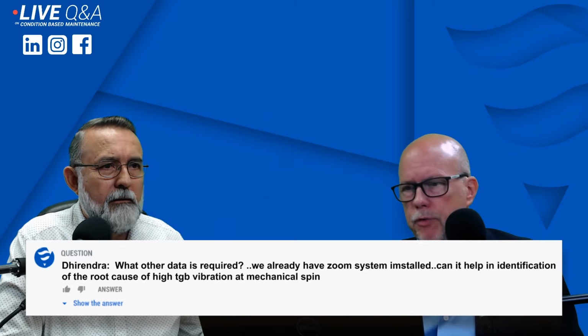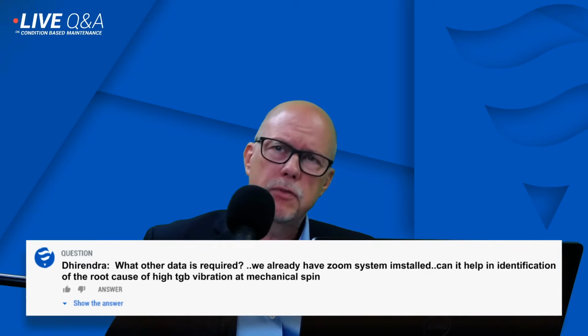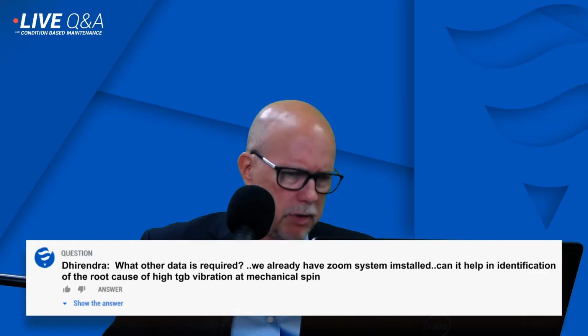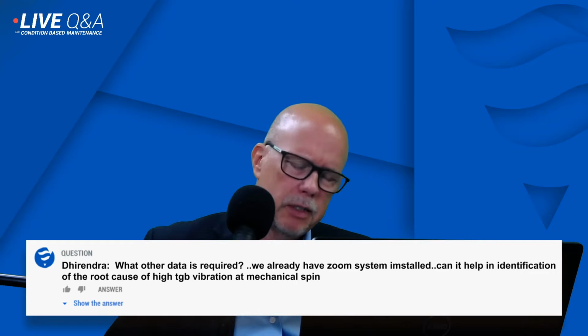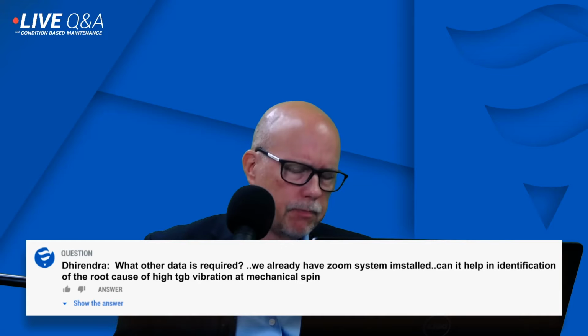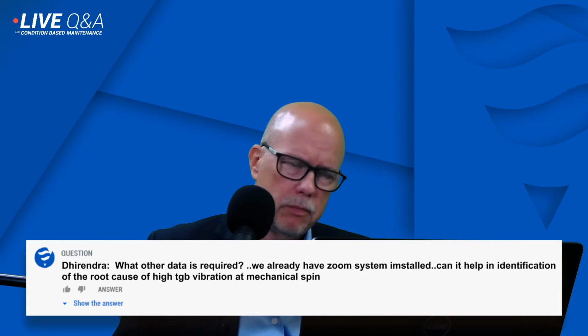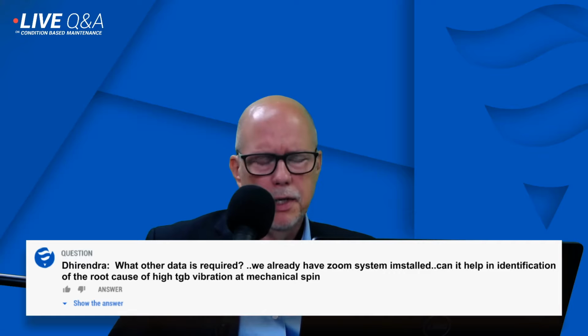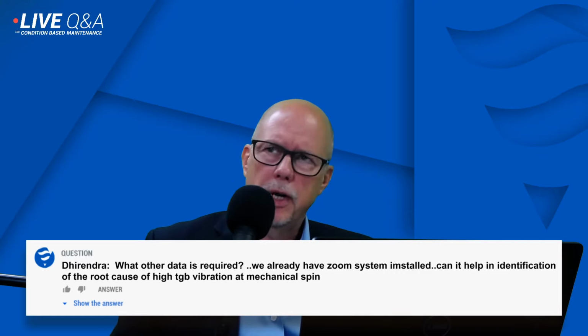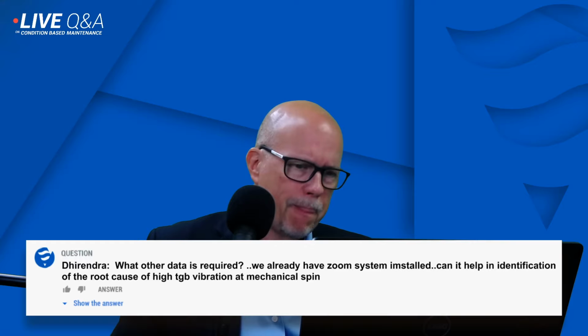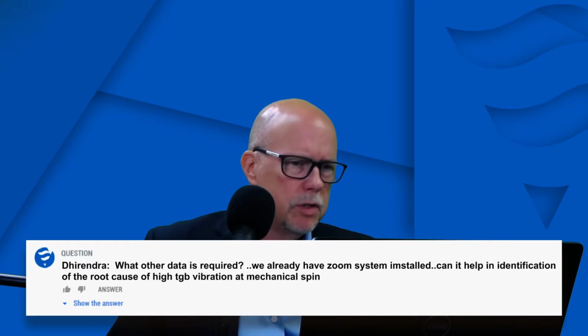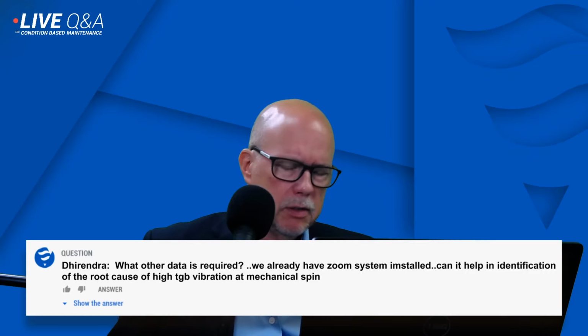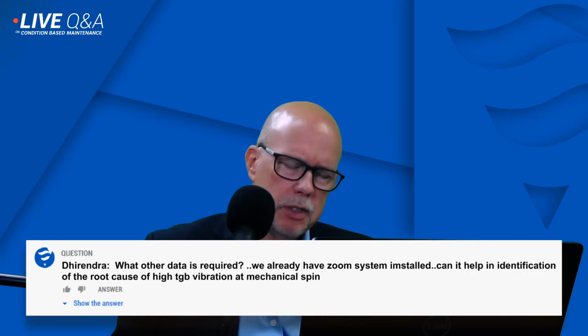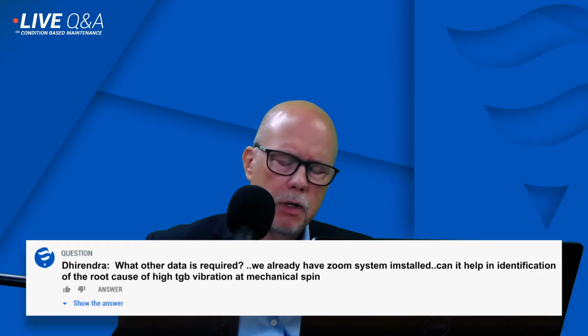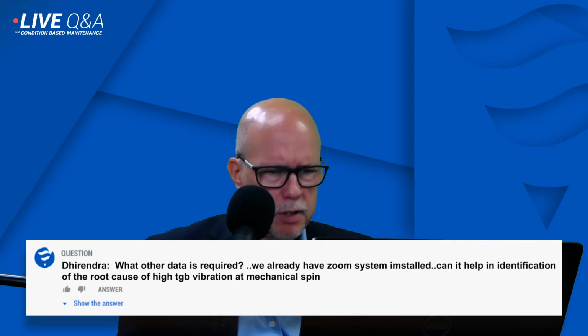Well, there's quite a few possibilities. I find it very curious that the turbine is very high, but the others are low when they're running at speed no load. Usually they're either all at the same amplitude, or the upper guide bearing or lower guide bearing should be higher. I would be interested to see the results at all the different operating conditions and see if we can pinpoint exactly what's going on. As I mentioned, the axial displacement might be an interesting thing to look at.